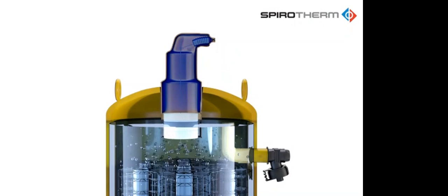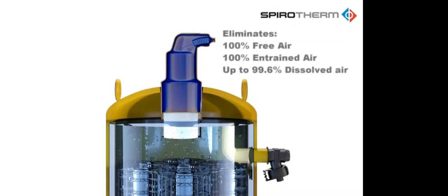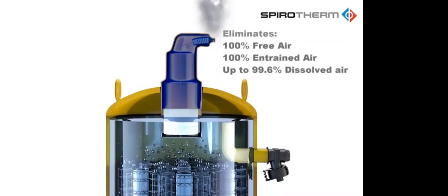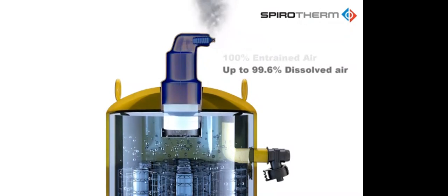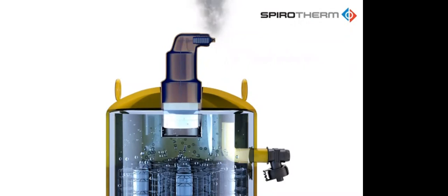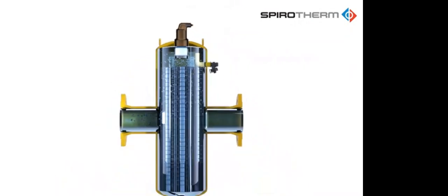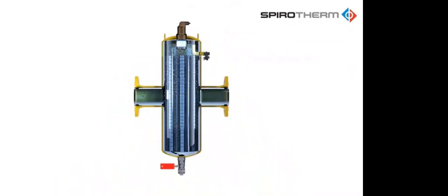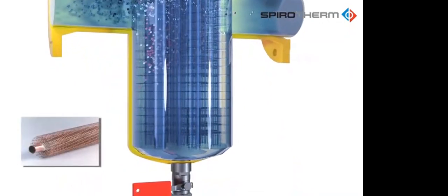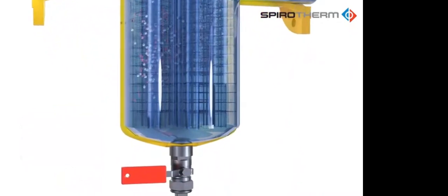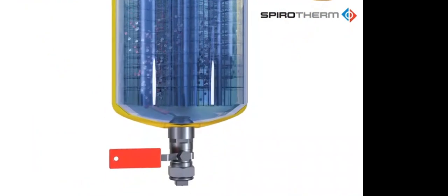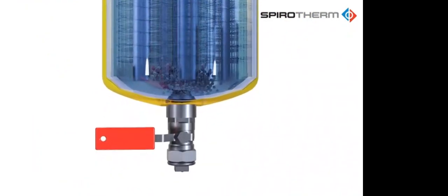Air problems become a thing of the past. Spirotherm is capable of scrubbing 100% of the free and entrained air and up to 99.6% of the dissolved air, making the water absorptive throughout the system. All while the air is being eliminated, the patented Spirotube causes dirt particles of all sizes to sink to the bottom of the unit and collect in the dirt chamber, eliminating any blockage concerns.